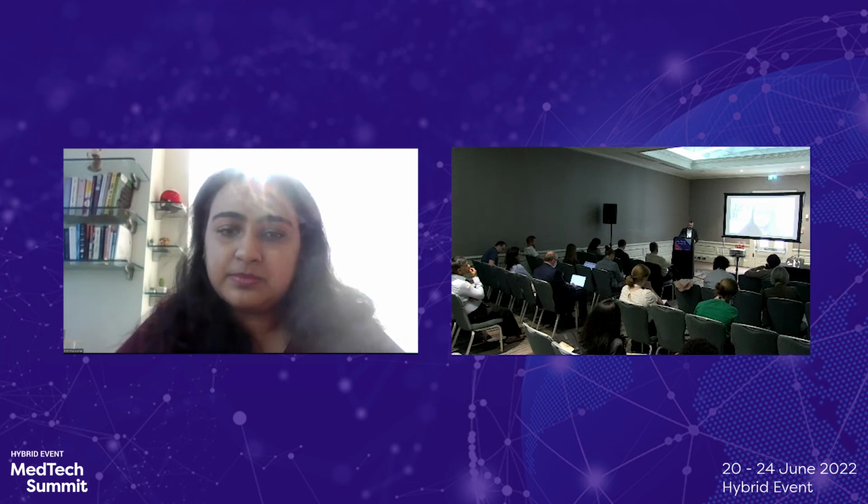So it's important to keep those requirements in mind, and as long as we can, follow. For example, for clinical investigations, the SSCP has very specific requirements for summarizing your clinical investigations. If we follow the same format for the CER, then we don't need to do it twice. So we just need to keep in mind that the requirements may be slightly different. Look into that a little bit, but definitely this graphic can be used as a reference to develop and align your deliverables.